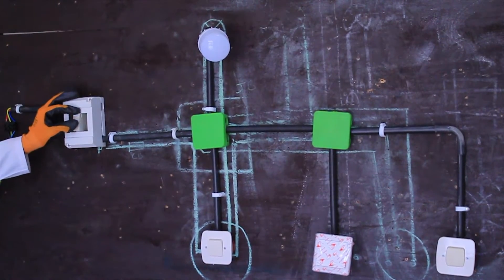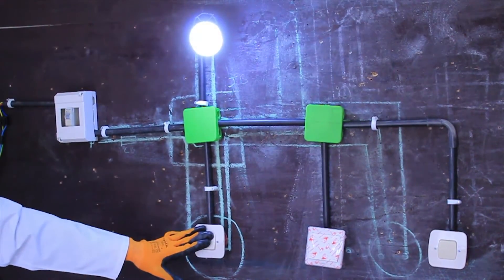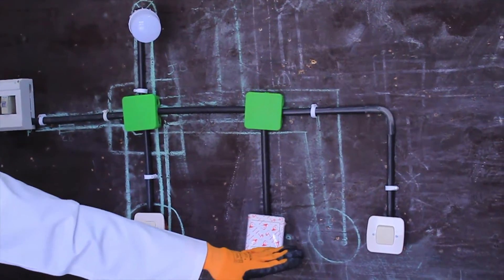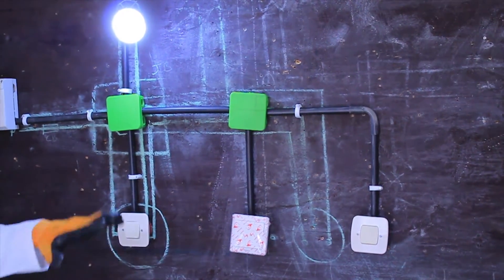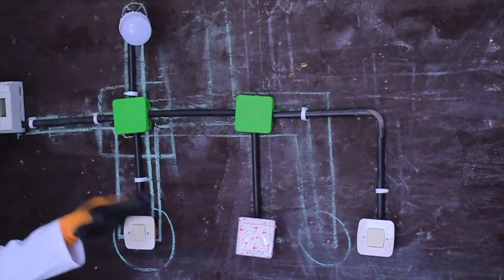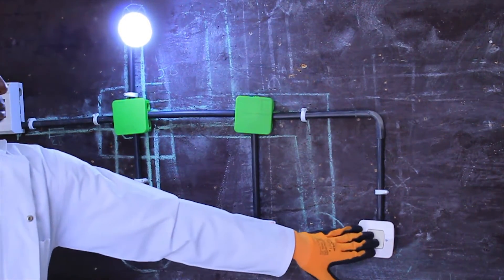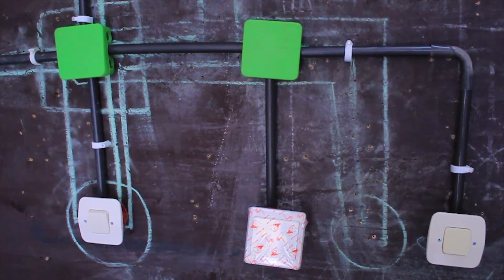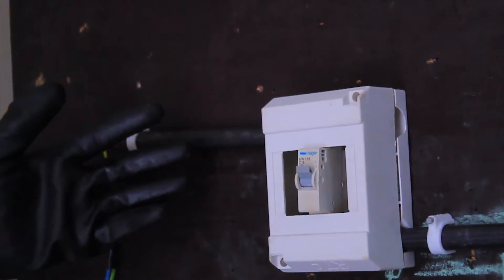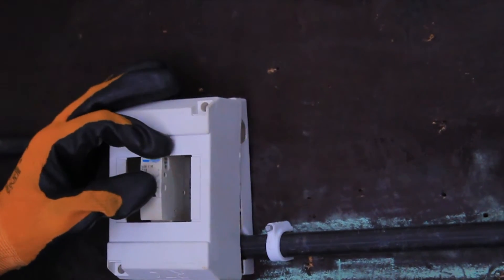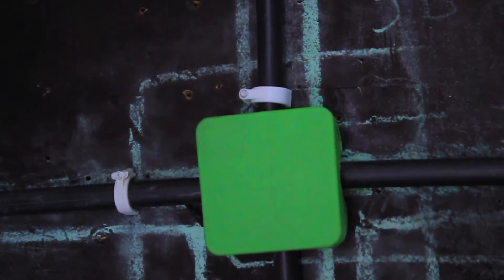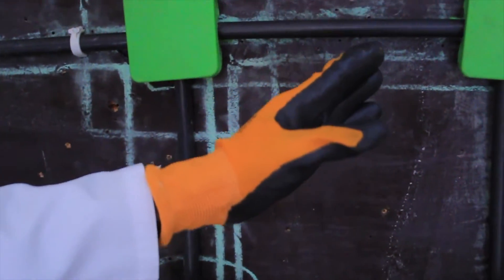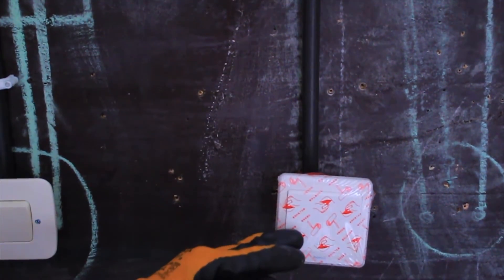As we go through this together, I hope you remember what we learned in our first and second sessions, and I hope you are doing the practical exercise with me. As you can see, we have accomplished the task of installing an intermediate circuit which has three different switches. This circuit shows how a lamp can be controlled from three locations, providing on and off control from each location. This circuit is used in places such as stairways, corridors, and rooms with more than two doorways. If more than three switching locations are required, it is simply necessary to add extra intermediate type switches.